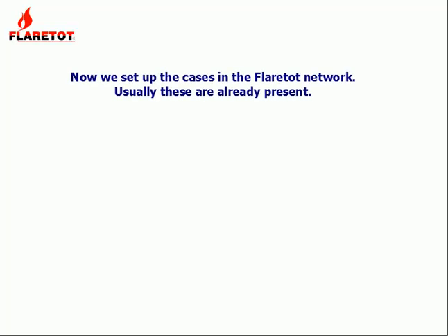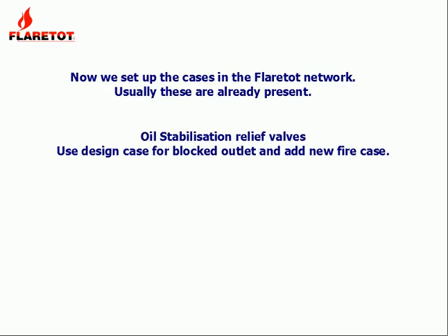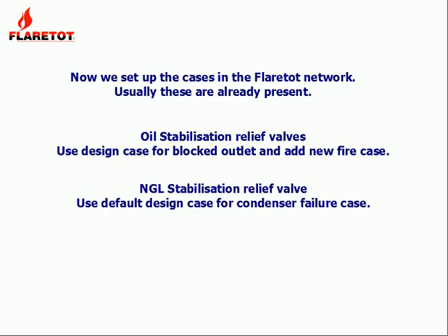Now we set up the cases in the Flaretot network, so we can import the stream data. This only needs to be done once. If Petro-SIM data is revised, data can be imported again. The oil stabilization relief valves each require a new fire case. The default design case can be used for the blocked outlet. The NGL stabilization relief valve condenser failure case can use the default design case.